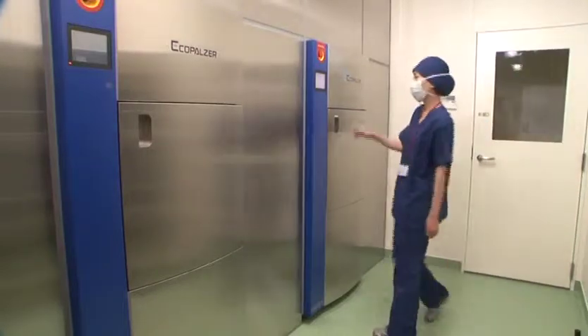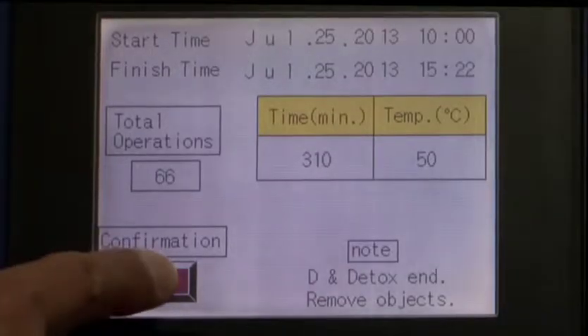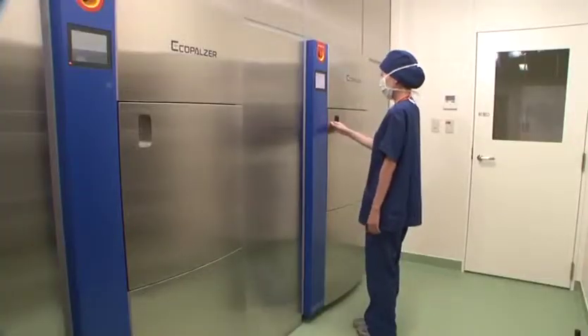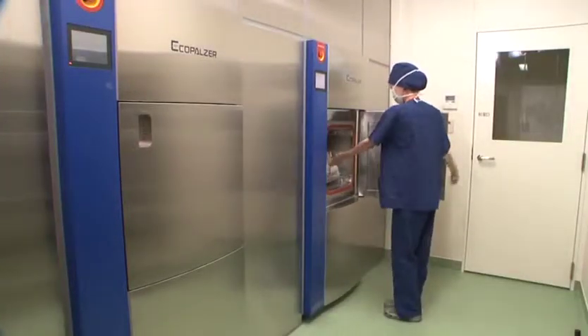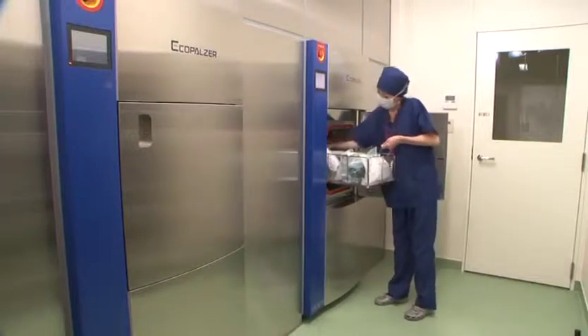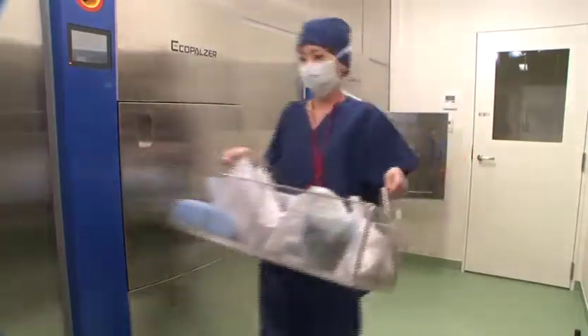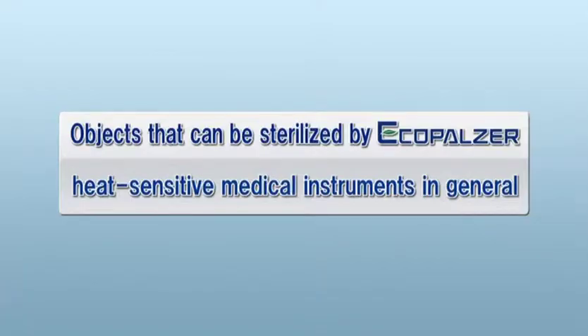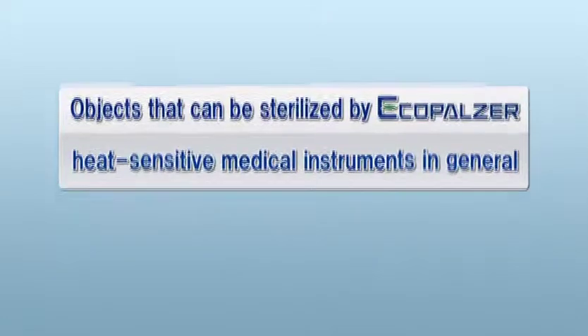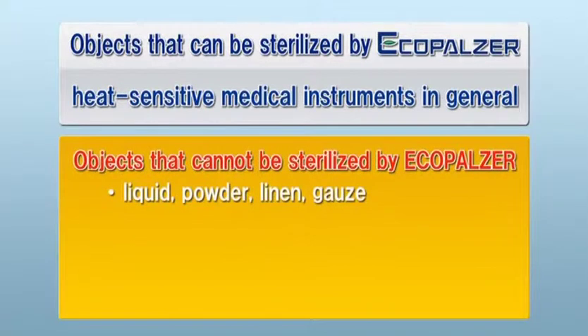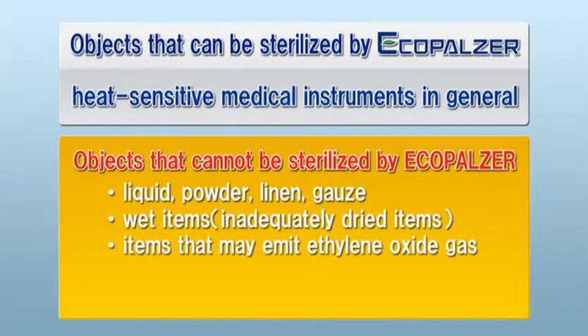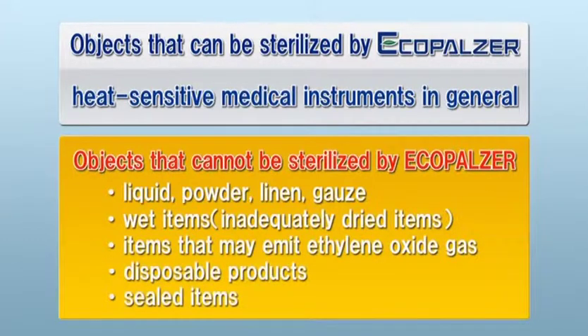After the sterilization cycle is completed in 310 minutes, open the door of the chamber and take out the basket holding the sterilized bags. The full process has now been completed. You can sterilize a wide range of heat-sensitive medical instruments and devices. Items that cannot be sterilized include liquid, powder, gauze, wet or sealed items, pressure-sensitive items, and things that could emit ethylene oxide gas.